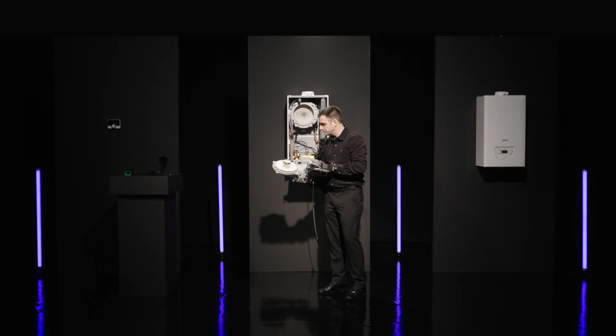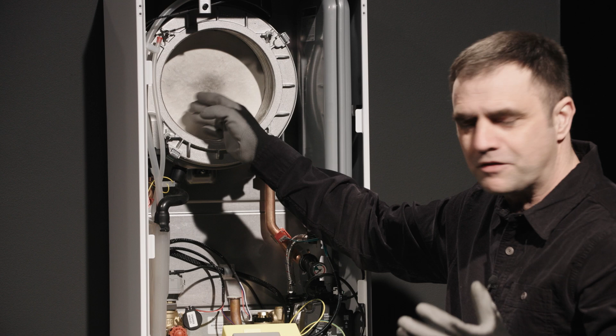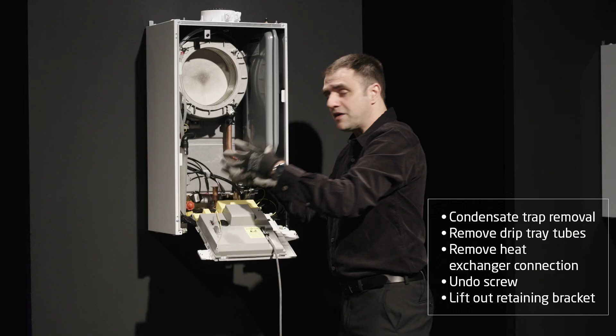And then I've got my fan assembly and my gas valve. Now all of these are available as a separate item, so you don't have to buy the whole combustion unit. You can get each item individually. Then I'm going to be looking at my heat exchanger, so I'm going to be putting a brush around that, cleaning it all out, pouring any water through there, and it's going to go down into my condensate trap and run away. If I need to remove the condensate trap, I quite simply take the tubes off the top, coming down from my drip tray up there, and I remove the connection from my heat exchanger, and then it's just one screw at the bottom.